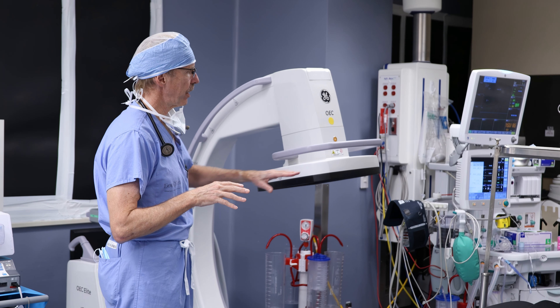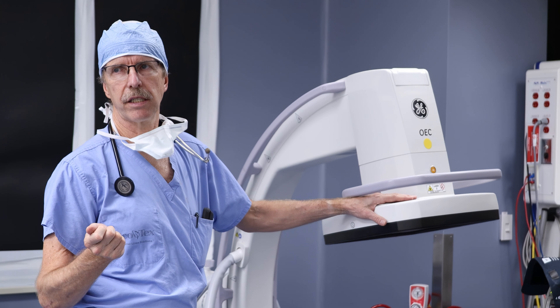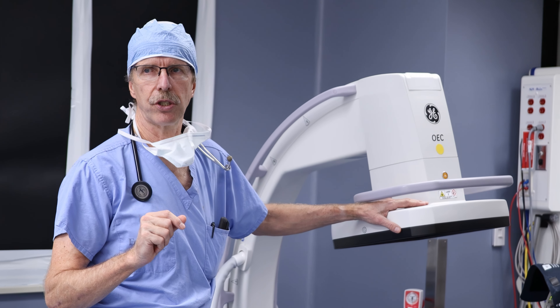The portable system gives us the option of working in any room, and the camera would also allow us potentially to do ablation procedures. What's different about this is the collector is much, much more sensitive, so that we can see with less x-ray, much clearer pictures.